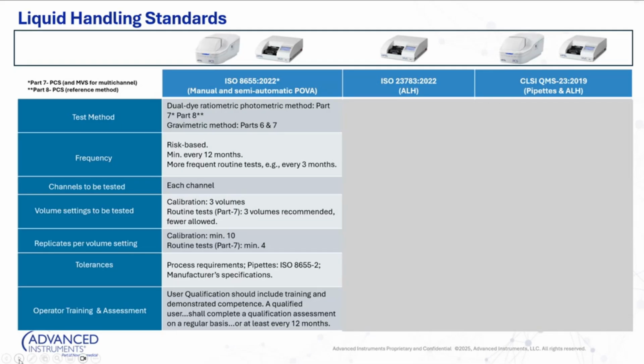And then with regards to volume settings, what volumes do you intend to test? If you have an adjustable device, especially an adjustable pipette, calibrations should involve testing at the low volume, the mid volume, and the high volume. But if you're just performing routine tests, you could have fewer volume settings that you're testing. Maybe you decide to test just at the low and the high volume. And of course, what you don't see if you do that is you won't be able to get to a linearity answer, if you will. But those routine tests are really just meant to be a quick check of that device.